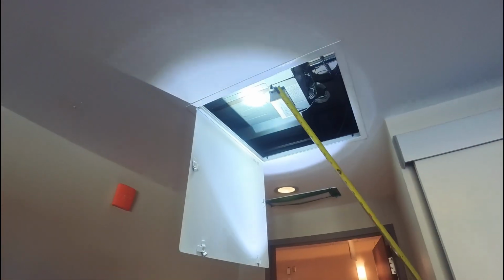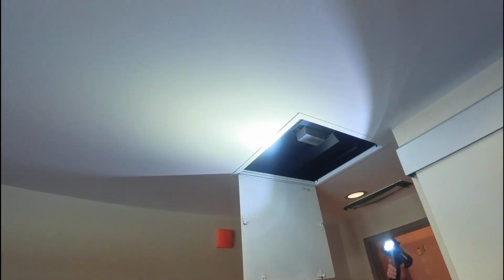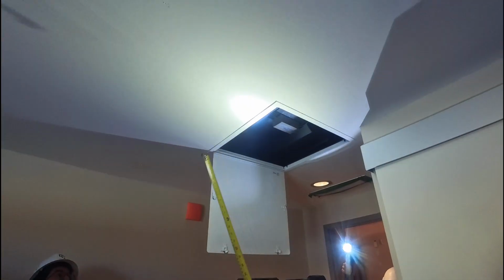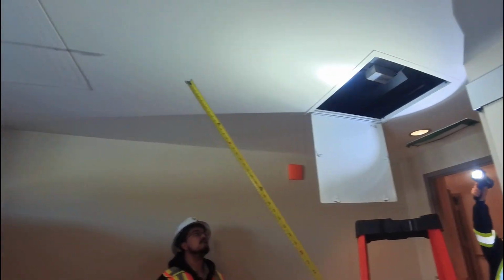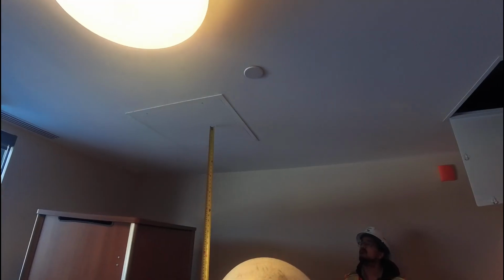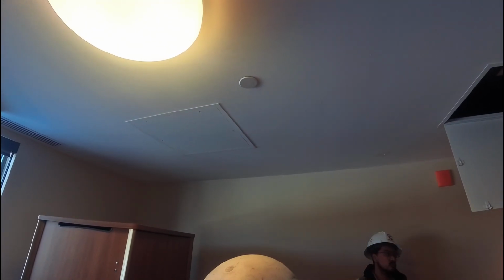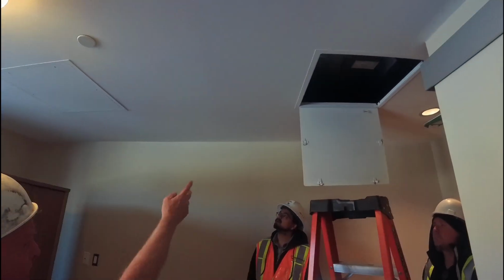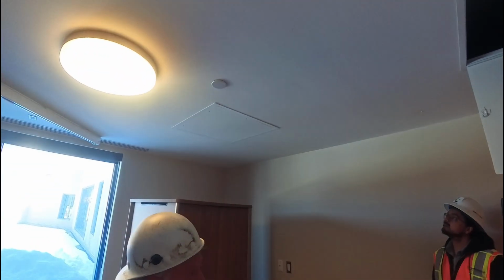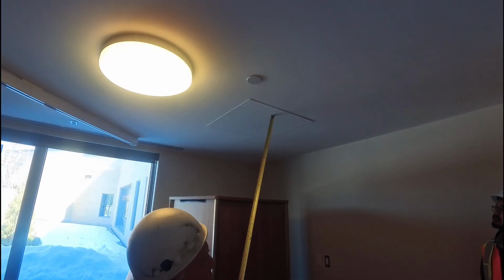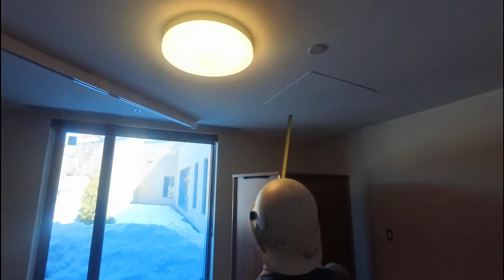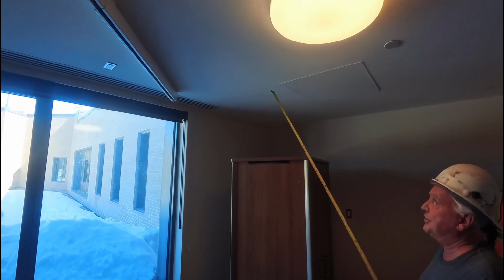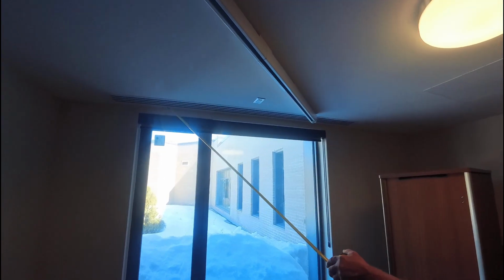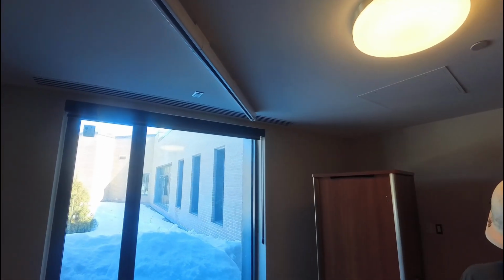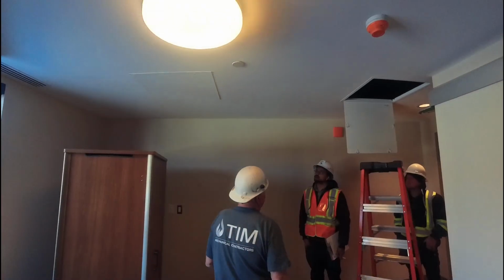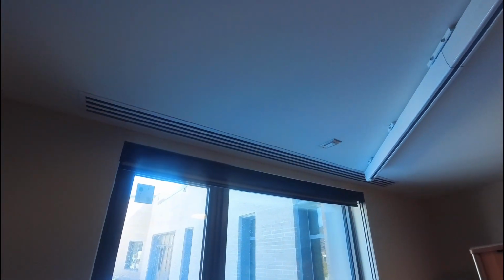And on the supply end of the fan coil unit, there's a similar door with the exact same setup where the filters are installed. What happens is on the supply end of it, at this access door, there's a duct heater which is used in case the temperature outside is too cold for the heat pump to get any air or heat out of it. It's assisted by this duct heater, and after the duct heater, of course, are a couple of round connections that go to, once again in the suites, we've used a linear style diffuser. It's very attractive.